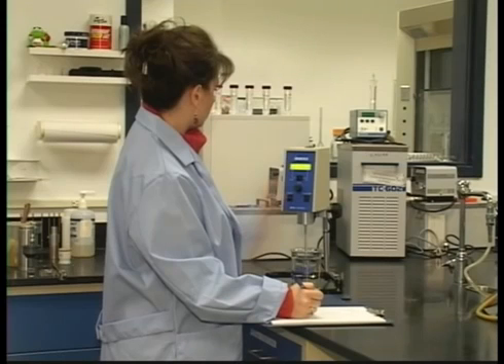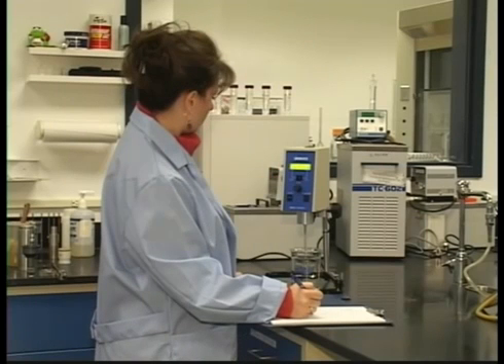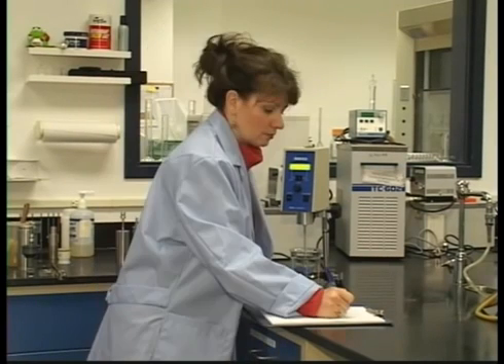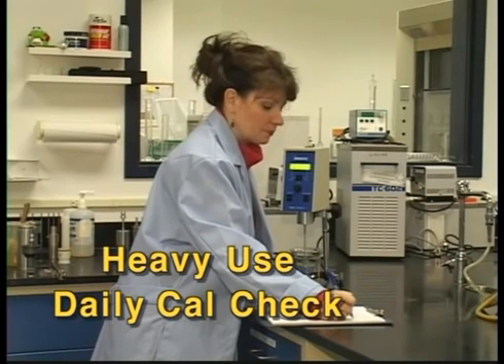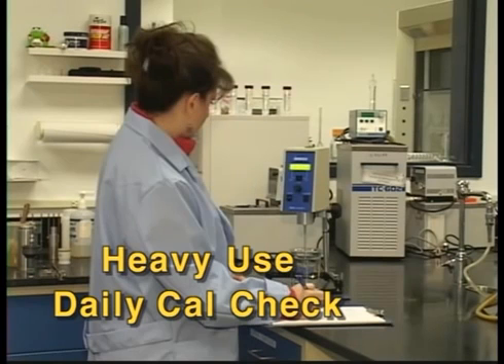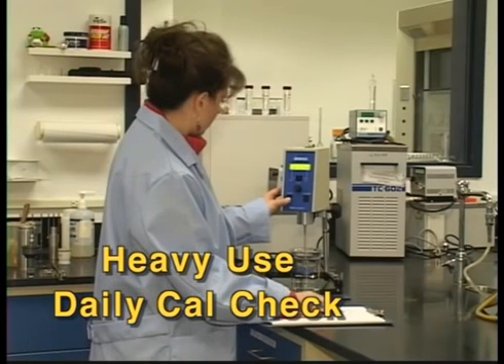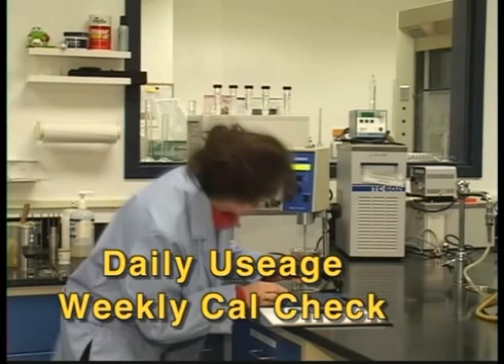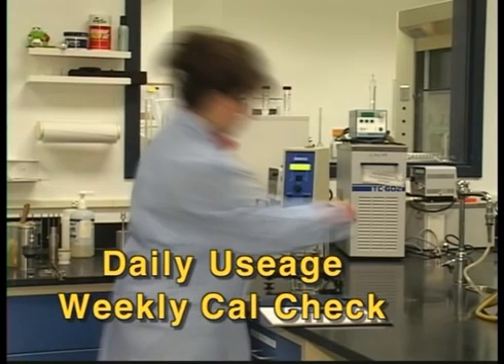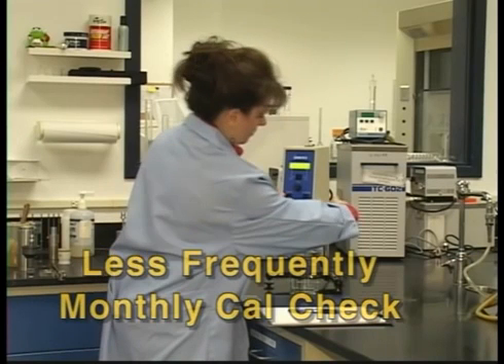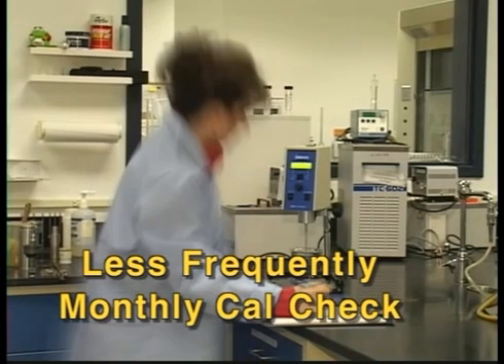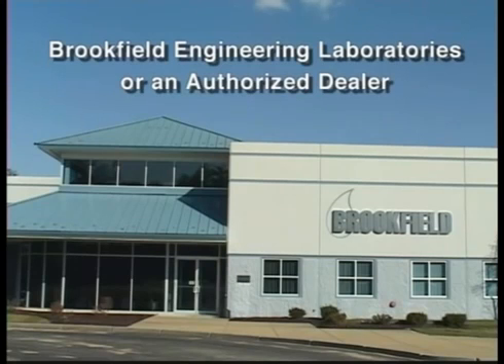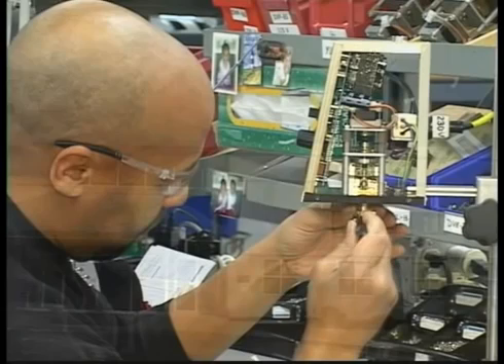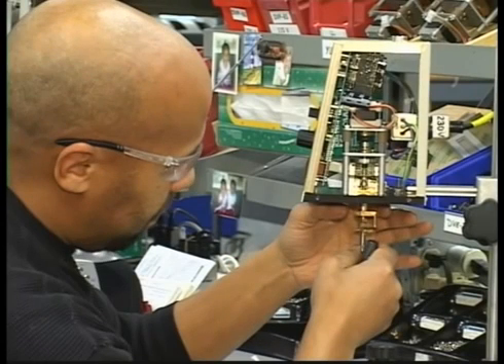A common question is, how often should a calibration check be run? The answer is really up to how often the instrument is used. For example, if an instrument is being heavily used, say on multiple shifts, a daily calibration would ensure accuracy. Daily usage, 5 days a week, may require a calibration check be performed at least once a week. For instruments used less frequently, perhaps once a month or once every few months will be fine. But to ensure the health of your instrument for many years, return this to Brookfield or an authorized dealer once a year for a full calibration, certification, and cleaning.